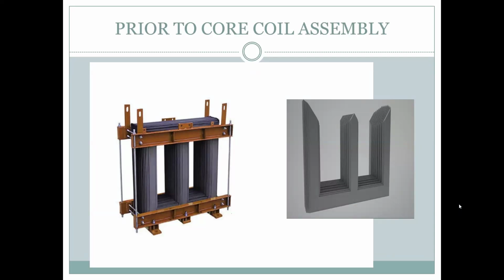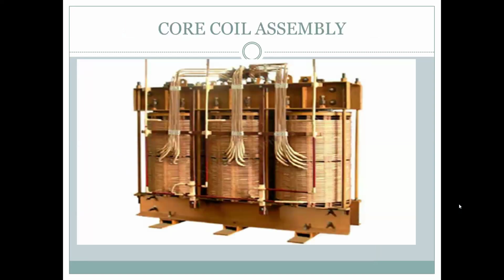The winding has come. Now you have to open the upper clamp, that is called the yoke. This yoke is opened up. Then all those limbs are to be put inside, and again clamped. The yoke is put back and then the core coil assembly is made. Next slide. This becomes a core coil assembly.